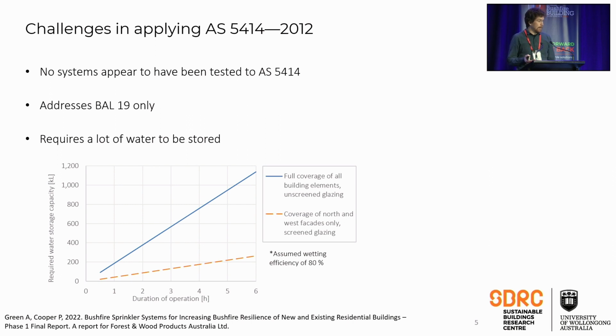Looking at AS 5414, there are some challenges in applying it, based on feedback from interviews with the community. To begin with, no systems appear to have been tested to Appendix A, which requires the sprinkler arrangement and type to have been tested using fans, to determine where the water ends up when sprayed. So as far as we can tell, without any systems having been tested, no one can currently comply with the standard - although I'd be very keen to talk to anyone who has tested systems.